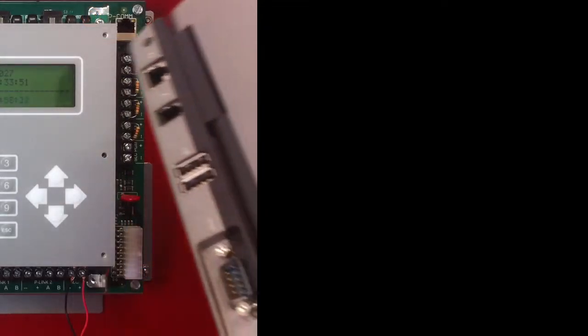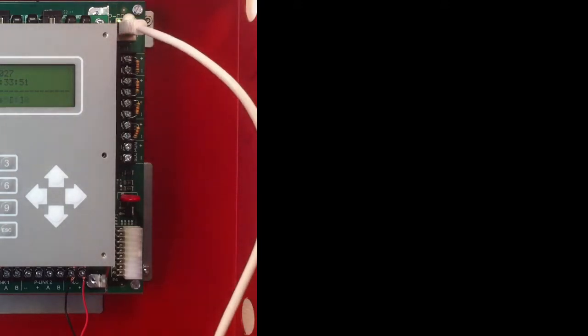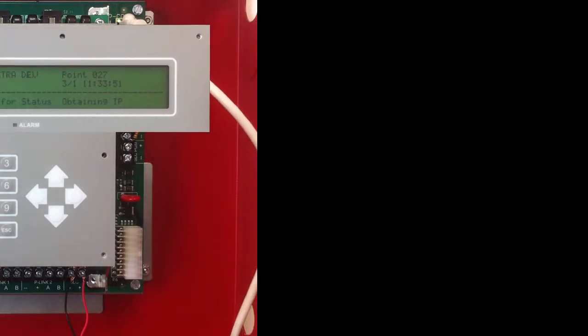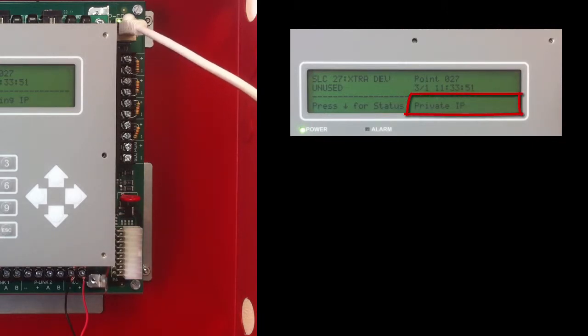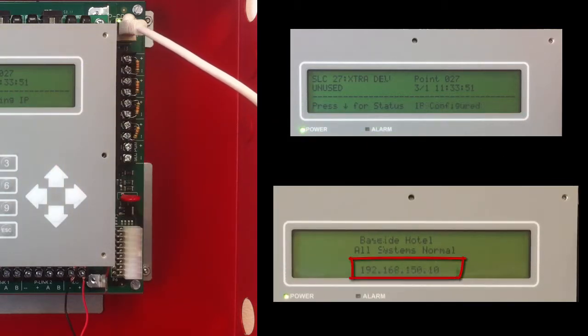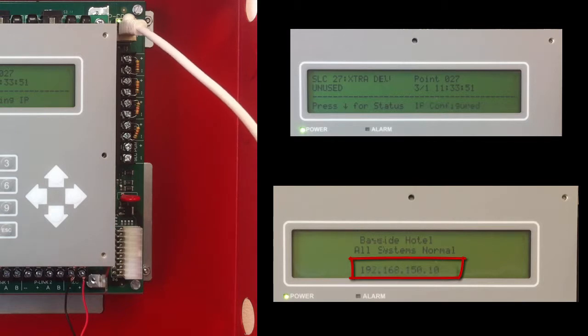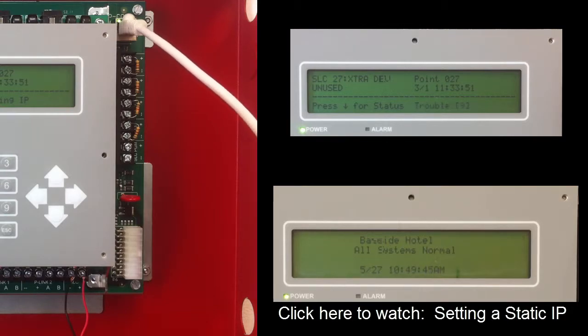When you are direct connected from the fire alarm control panel's PCOM connection to the ethernet jack on your computer, the panel and computer are on a private network and the panel should show an IP address of 169.254.150.70. All Potter PFC addressable fire alarm panels out of the box have an IP address on a private network of 169.254.150.70. If a static IP has been set, then you will see that IP address instead of the 169.254 IP address. To learn how to set a static IP address at the fire alarm control panel, please refer to the video "Setting a Static IP Address."